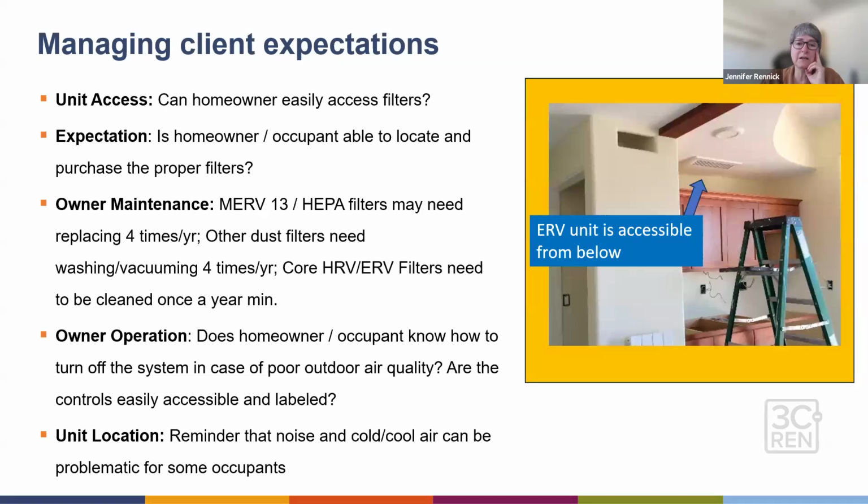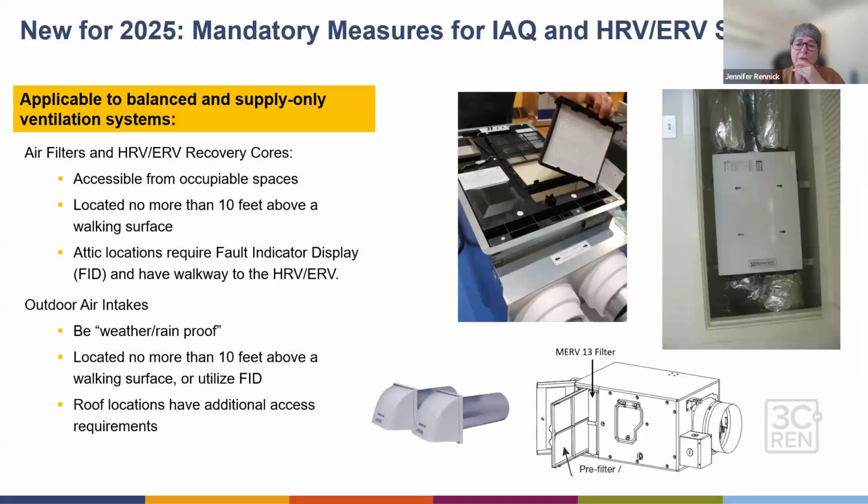The ventilation isn't really a big number. It's really pretty small. And one of the builders we work with for retrofits, because there isn't a code requirement on it, you can use through-the-wall ventilation systems too, where they operate in pairs. But for getting credit for new construction, the fans themselves have to be HVI rated, and some of those through-the-wall spot ventilation systems are not yet. But this Panasonic spot ventilation is, and Broan makes one like it, where it's supply only.